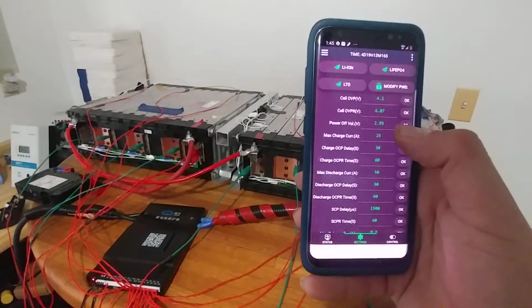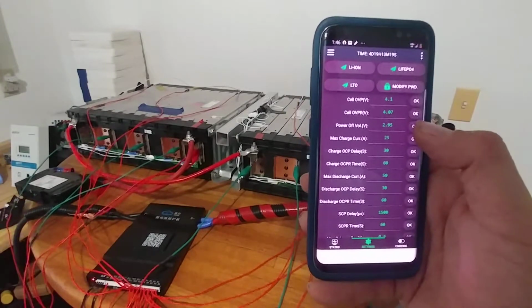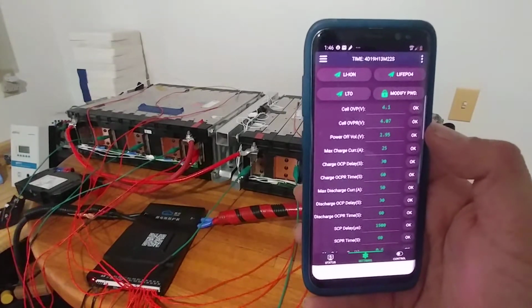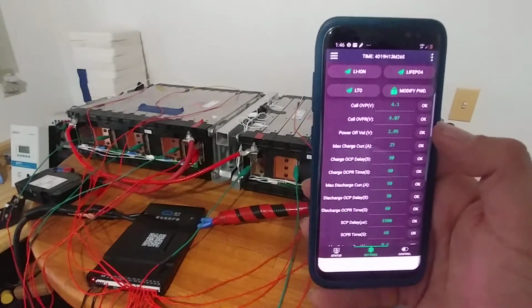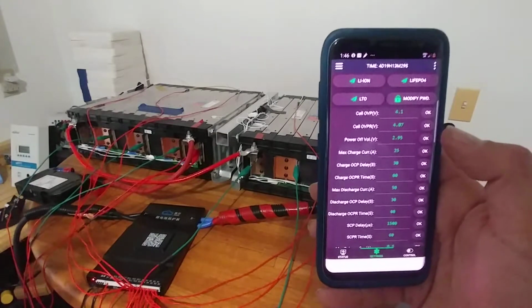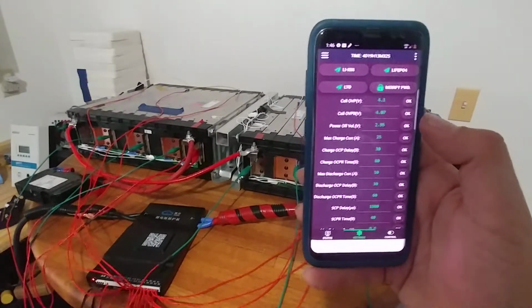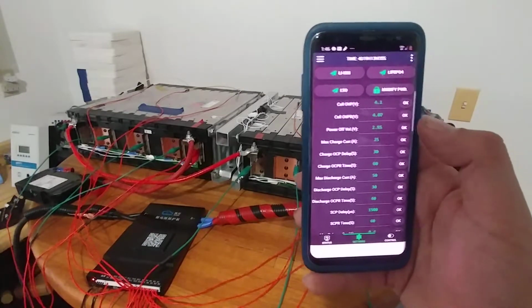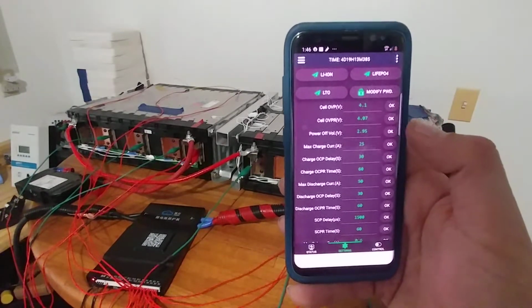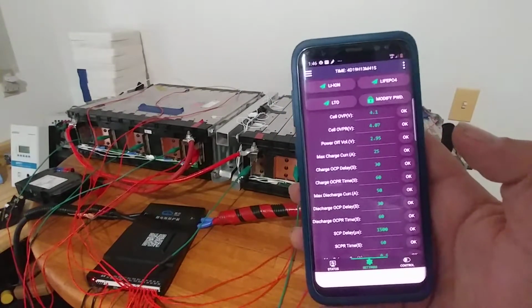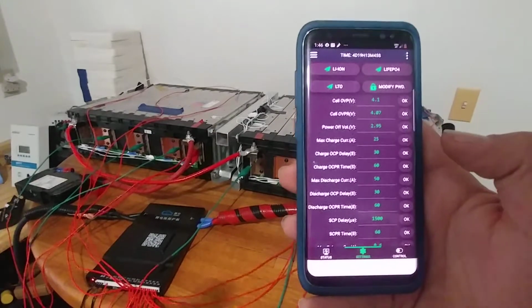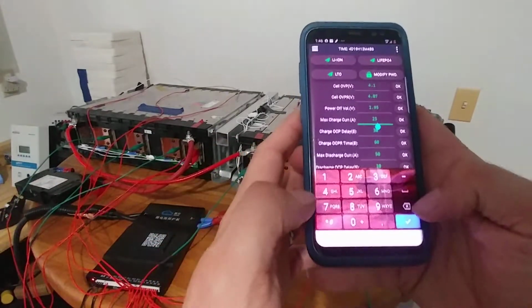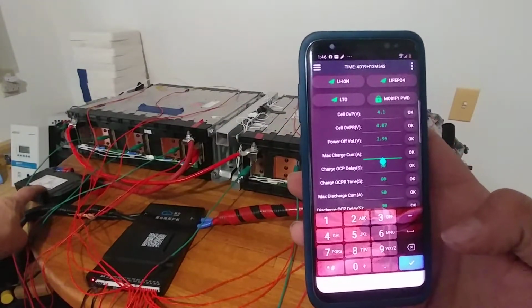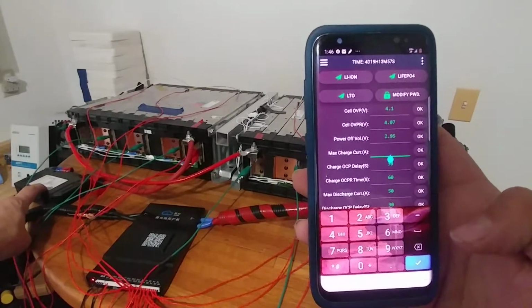This is the max charge current. Depending on which one you get, you actually have different charge and discharge capacities that they're rated for. And I'm unsure if the capacity that they're rated at is a surge capacity, or if that is the continuous. But I typically buy the one that is about twice the amps as I plan on using, because in that case you know it's going to be very happy just at a 50% load. But you could go ahead and change this to say, well, more accurately, this is a 125 amp breaker, which means that it'll trip at 156 amps, which is the rated value plus 25%.